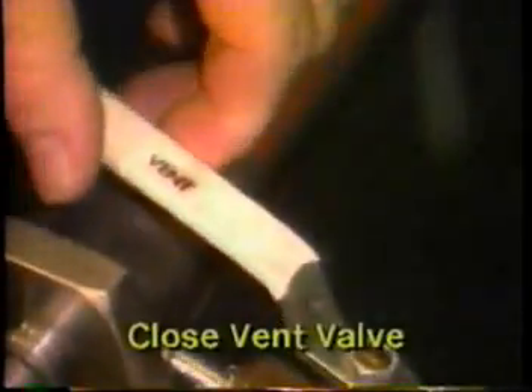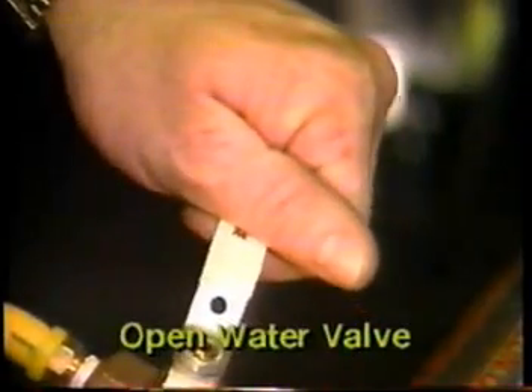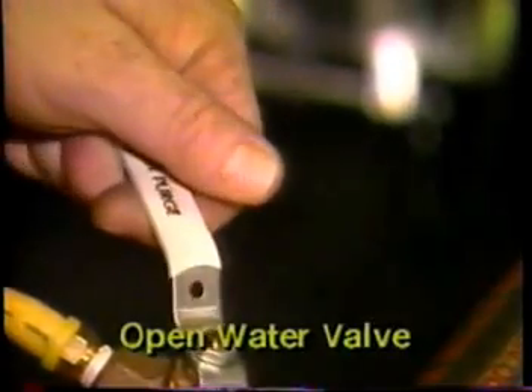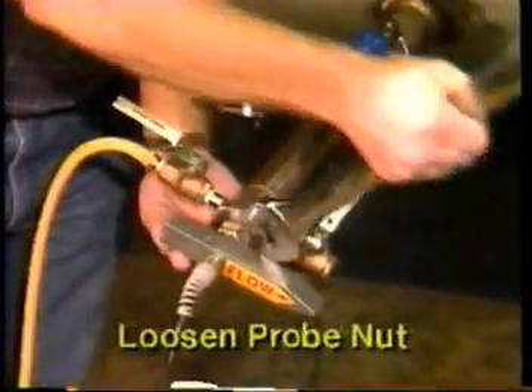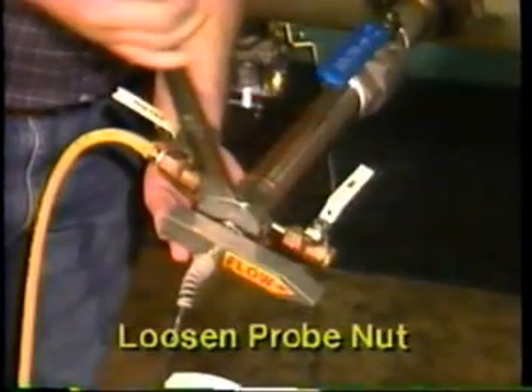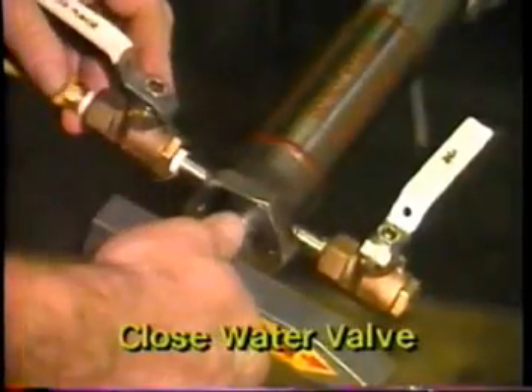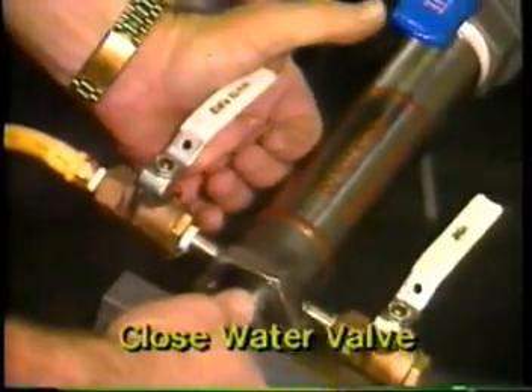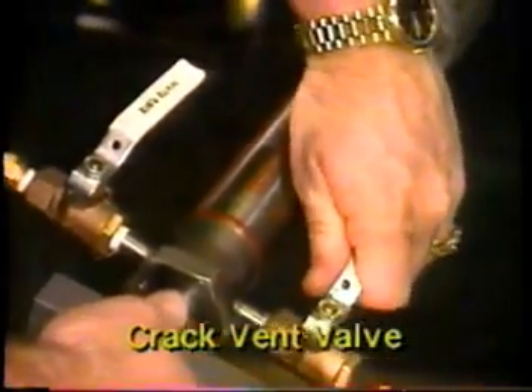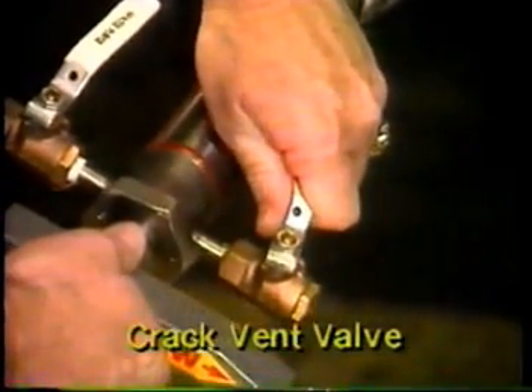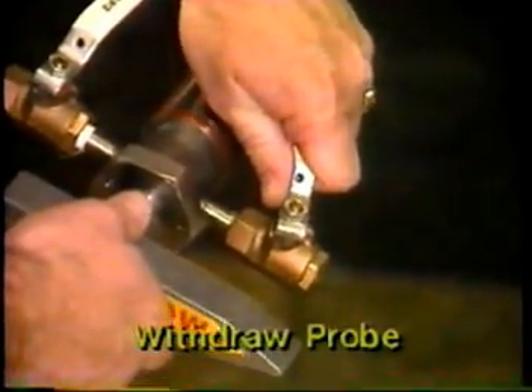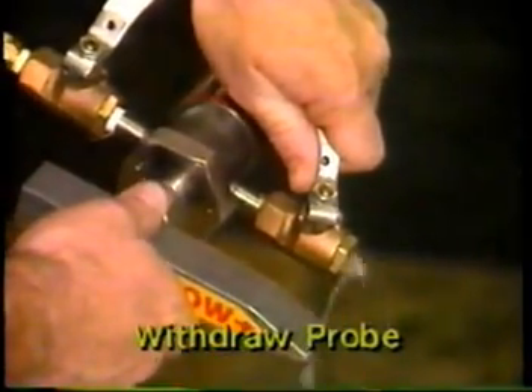First, close the vent valve. Open the water valve if not already open. Loosen the small nut over the probe extension. Now close the water valve. Open the vent valve slowly to bleed off the water pressure, at the same time withdrawing the probe until it clears the ball valve.